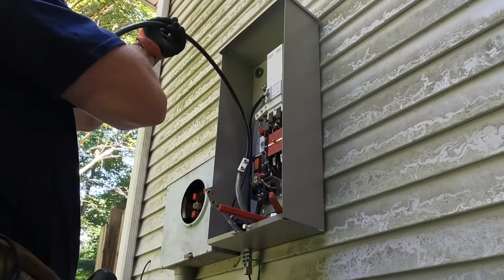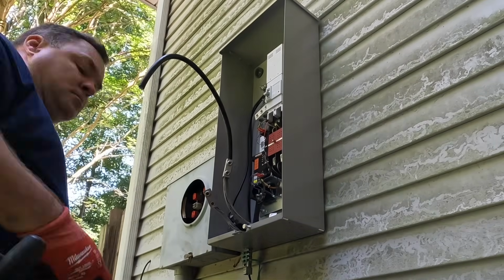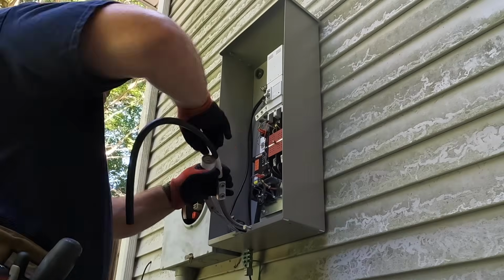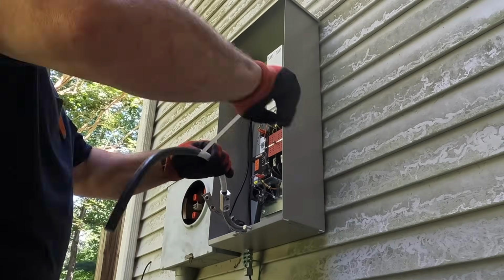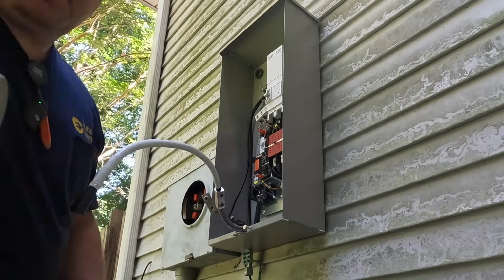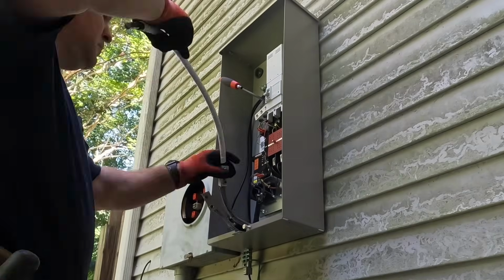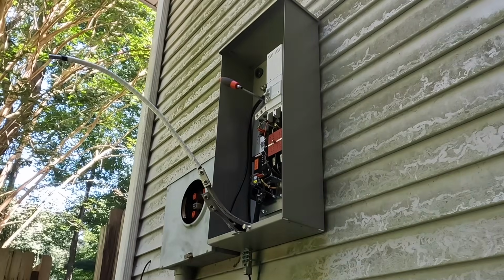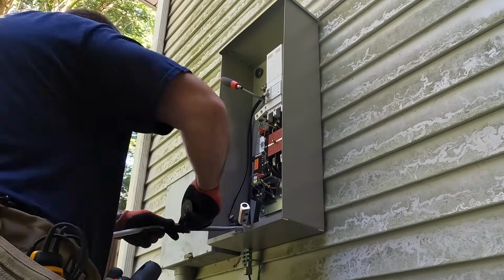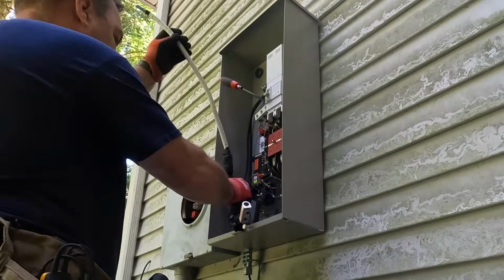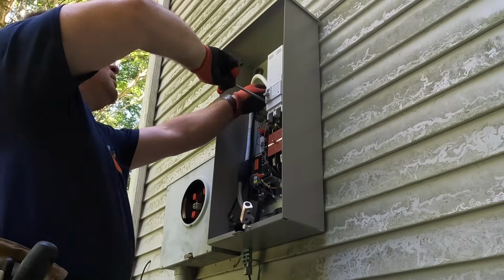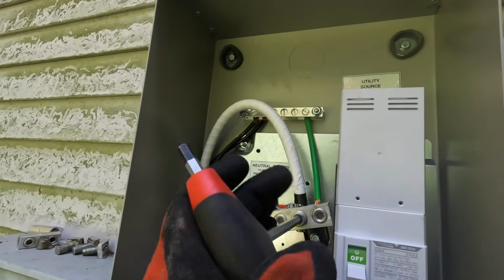There was no slack on this wire, and because the old disconnect had the lugs at the bottom, the lugs in this transfer switch are not in the same place, so I had to extend these conductors. There was no slack on the inside, and we can't put them into a junction box, although I guess we could. I chose not to. I chose to extend these conductors to the load side of my transfer switch.